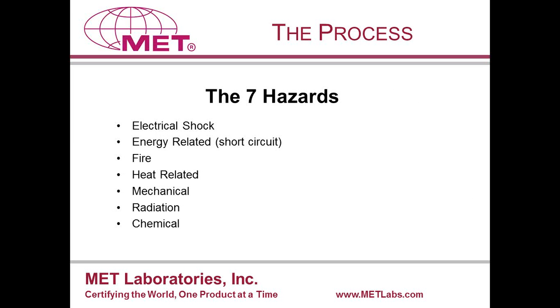So that gives you a basic understanding of the history of the program and the legal requirements. Now, what exactly happens during the testing and certification process? Safety standards address 7 areas or hazards that can exist with the use of electrical equipment. Safety standards exist to ensure that, as much as possible, these hazards are mitigated. Obviously, with electricity, there can be shocks to the user or problems caused by short circuits that can result in electrocution and fire. But there are also mechanical tests that address things like sharp edges or the ability of a finger to contact high voltage inside of an enclosure through the vents.